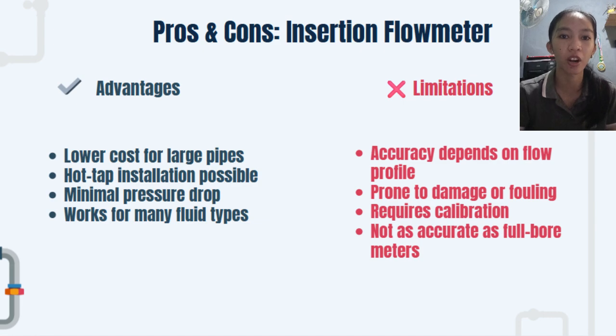However, the limitations are important. Their accuracy is highly dependent on a stable, predictable flow profile. If the flow is turbulent or asymmetric, the guesswork gets worse. Then, the probe is exposed and can be damaged by high velocity or particulate matter. And also, they typically require calibration to the specific pipe and flow conditions. Lastly, they are generally less accurate than full bore meters.